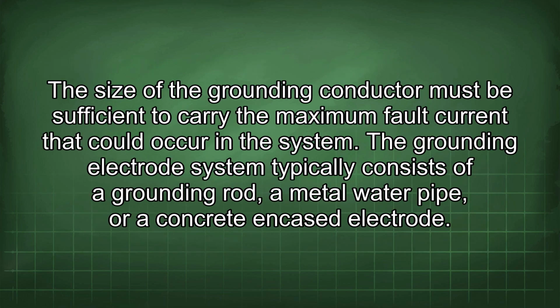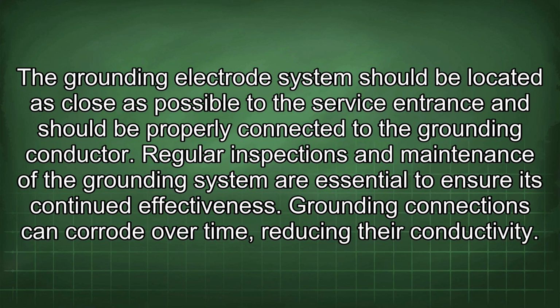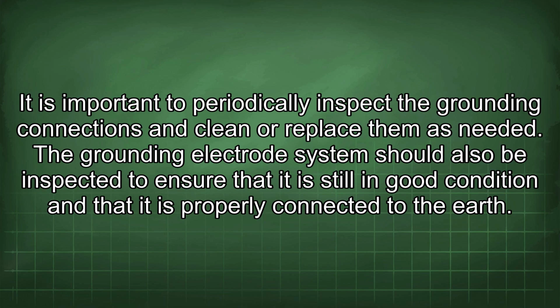The size of the grounding conductor must be sufficient to carry the maximum fault current that could occur in the system. The grounding electrode system typically consists of a grounding rod, a metal water pipe, or a concrete encased electrode. The grounding electrode system should be located as close as possible to the service entrance and should be properly connected to the grounding conductor. Regular inspections and maintenance of the grounding system are essential to ensure its continued effectiveness. Grounding connections can corrode over time, reducing their conductivity. It is important to periodically inspect the grounding connections and clean or replace them as needed. The grounding electrode system should also be inspected to ensure that it is still in good condition and that it is properly connected to the earth.